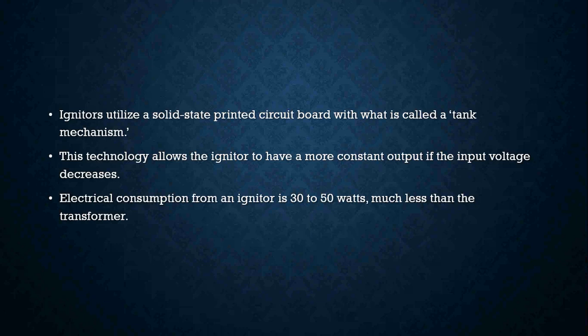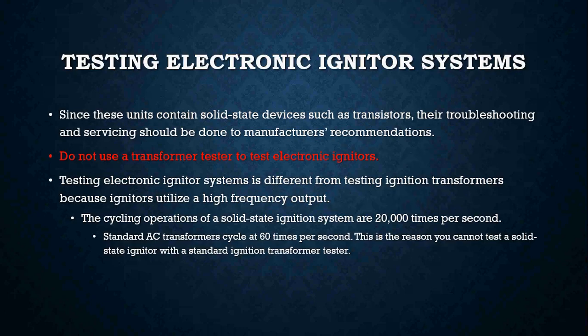So what we're saying there is that if you have a little bit of a voltage spike or you lose some voltage on the primary side, it really doesn't affect that secondary output that's coming out of the output side of these types of guys. It remains relatively constant. Electrical consumption from an igniter is anywhere between 30 to about 50 watts, much less than what an ignition transformer is going to be using.